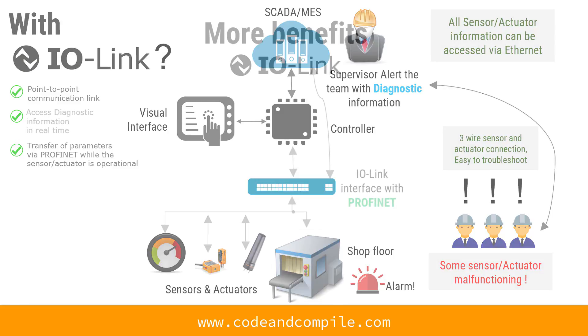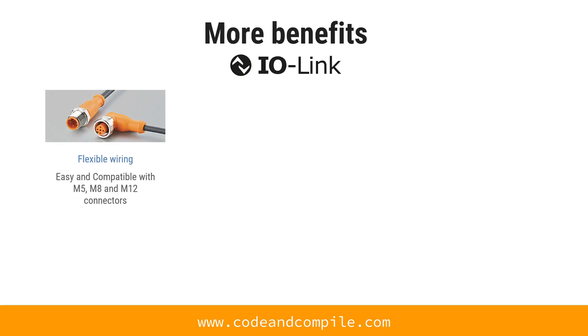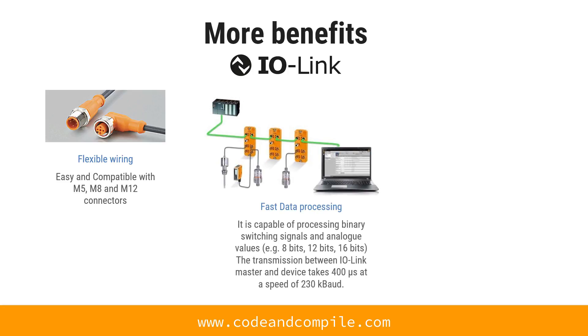Now let's look at more benefits of IO-Link. The first benefit is flexible wiring — you can easily connect your IO-Link sensors and actuators via M5, M8, and M12 connectors. Second, you have fast data processing: it is capable of processing 8-bit, 12-bit, and 16-bit data in just 400 microseconds.